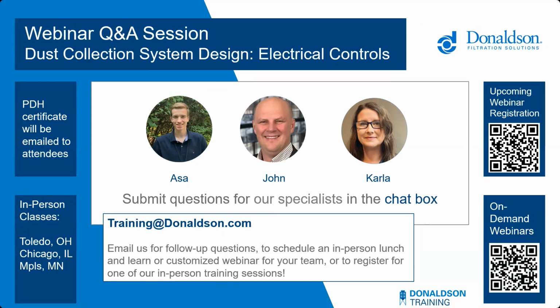Thank you, Karla. So the next one, Asa, this is probably for you. Can you touch on the difference between Magnehelic and Photohelic pressure gauges and the pros and cons of that type that Donaldson offers? Yeah, that's a really good question. Magnehelic gauges are the most simple. You probably have seen them before. They are just a gauge that will output your differential pressure across the filters. There are two taps, one on the clean side, one on the dirty side, and we're taking the difference to find that value.